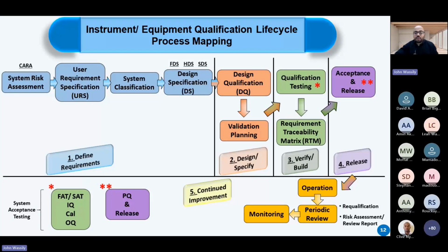For the equipment qualification, it's not a single or simple activity, it's actually a life cycle. And here I'm presenting to you a process map for this life cycle. It starts by performing a system risk assessment, performing a critical attributes and critical aspects risk assessment, listing all the aspects that are critical to the end product quality and patient safety. So by listing all those aspects, we'll be able to start drafting our user requirement specification for that piece of equipment.